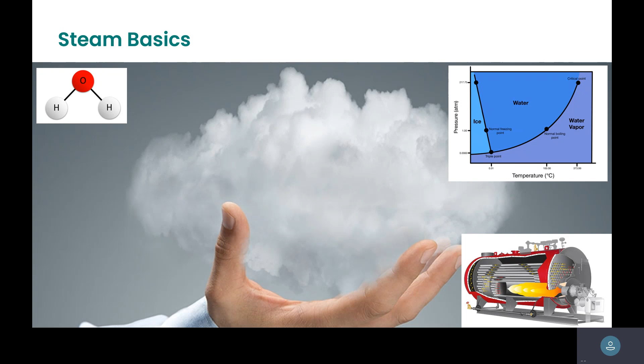So again, very basics, you have three levels of steam. You have dry steam, probably the easiest one to measure, because they treat it like any hot gas at that point. It's above the saturation lines. If you know the temperature, the pressure, the density, a lot of the mass flow calculations are done very simply. In this regime quality is one. Again, steam quality is the mass of gas to the total mass overall. This is the simplest application to handle because it's really treated as any hot gas overall.